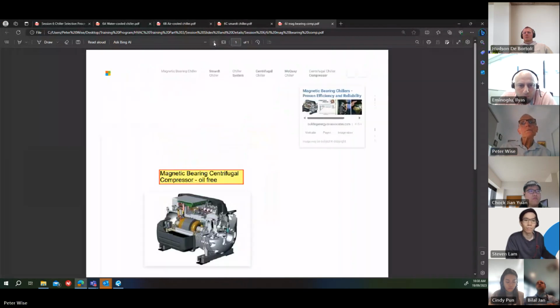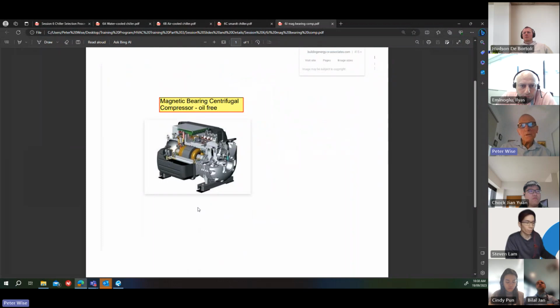Make that a bit bigger. This is the magnetic bearing compressor. The motor is hermetic; the motor's inside there. The refrigerant passes through. These compressors are oil-free, so they're probably the most efficient compressor available because there's no friction. The compressor is running on an air bearing. It's a magnetic bearing. It's not touching anything. It's just floating in the air because of the magnetic field, and there's no oil involved. So these are very popular now. But as I said, the maximum capacity is about 1,000 kilowatts. So you need multiple compressors if you're going to have a large chiller.